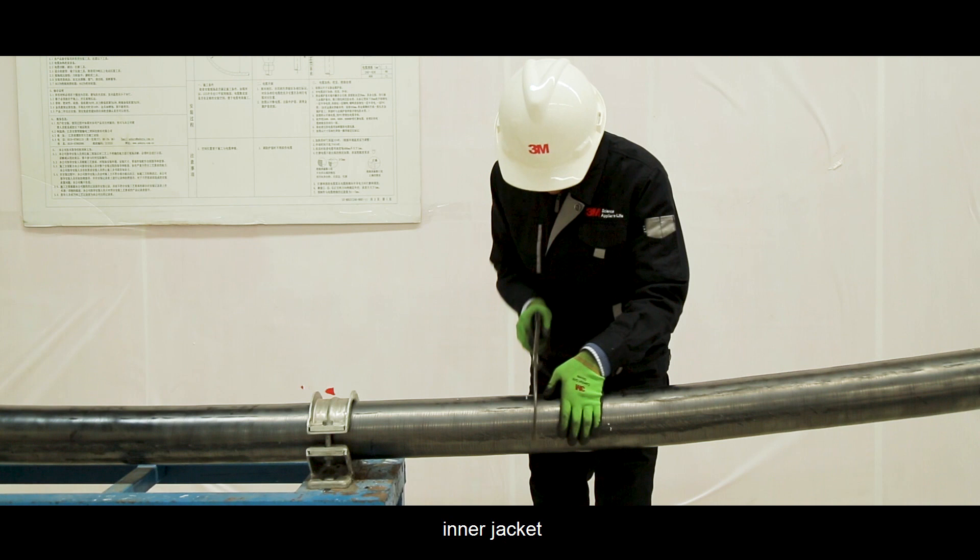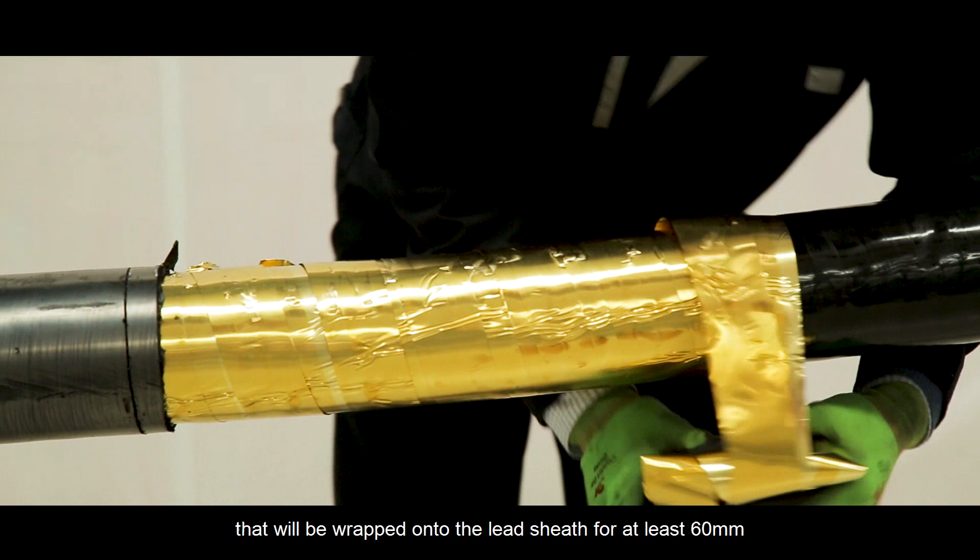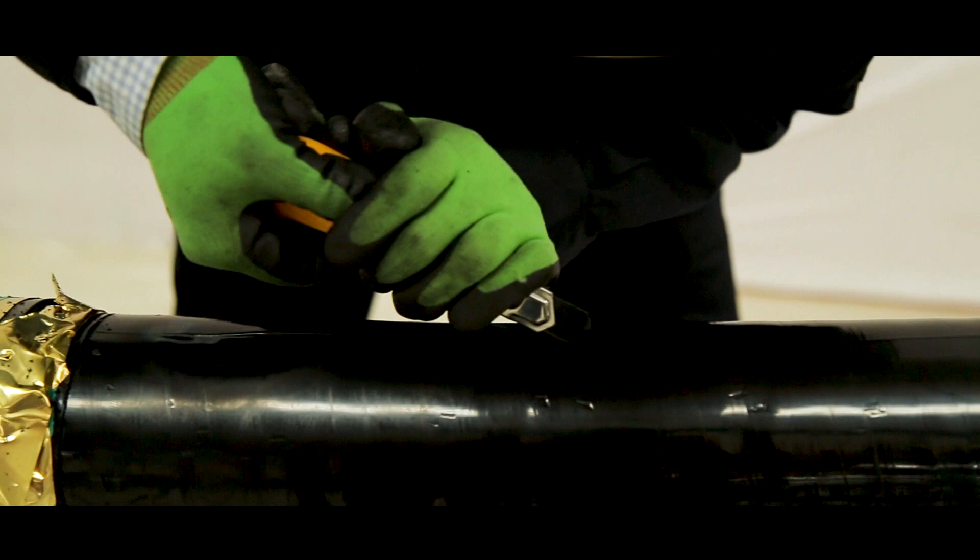Measure and remove the cable jacket, brass tape, inner jacket, and lead sheath according to installation drawing. Allow additional length of cable for adjustment. Keep sufficient length of brass tape that will be wrapped onto the lead sheath for at least 60mm.